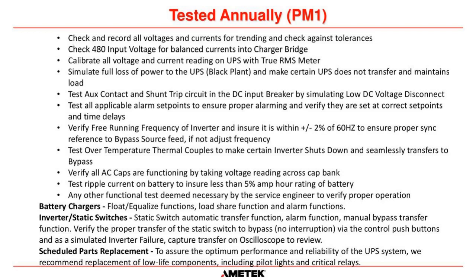Another thing that we do is we check the input current to the charger bridge for balanced currents. Now, a lot of people don't realize, but the secondary of our input transformer to our charger bridge is a delta connected transformer. Sorry, the primary. But the main point is the currents on that rectifier should be balanced. So on A phase, B phase, and C phase, let's say A phase is 10 amps, then B phase and C phase should be 10 amps. And if there is an unbalanced current, that shows there's an issue with the charger bridge. Maybe there's an SCR that is not firing, or there's a loose connection between the gate driver board and the charger bridge.